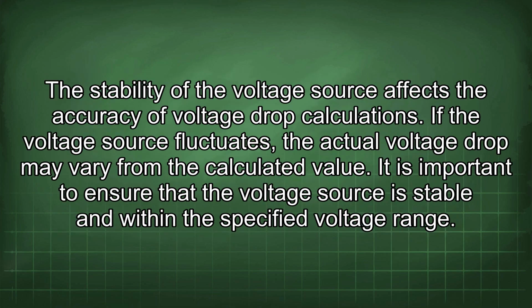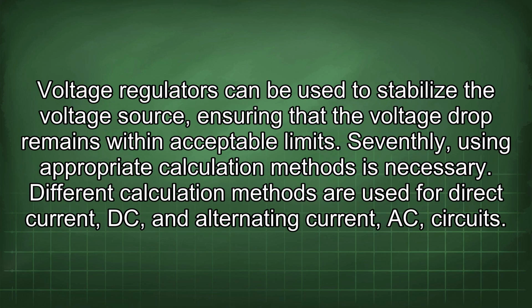Sixthly, voltage source stability is important. The stability of the voltage source affects the accuracy of voltage drop calculations. If the voltage source fluctuates, the actual voltage drop may vary from the calculated value. It is important to ensure that the voltage source is stable and within the specified voltage range. Voltage regulators can be used to stabilize the voltage source, ensuring that the voltage drop remains within acceptable limits.